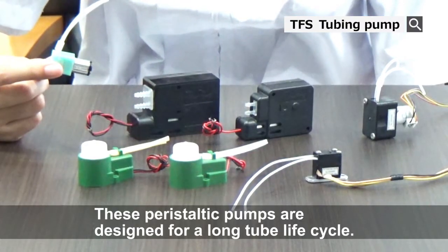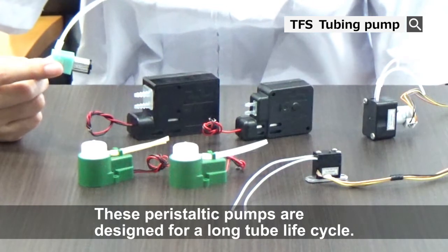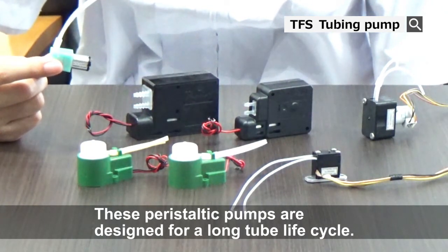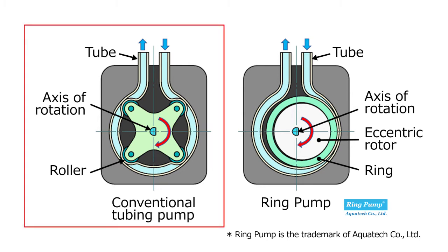The key feature of these peristaltic pumps is that they are designed for a long tube life cycle. Generally, as the picture shows on the left, the peristaltic pump delivers the fluid by compressing the tube with several small rollers.